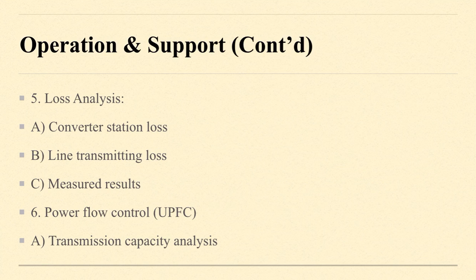Second is line transmitting loss. DC transmission lines include cables and overhead lines. A loss of cables is mainly caused by resistance. The losses of overhead lines mainly include corona losses related to voltage and resistance losses related to current.